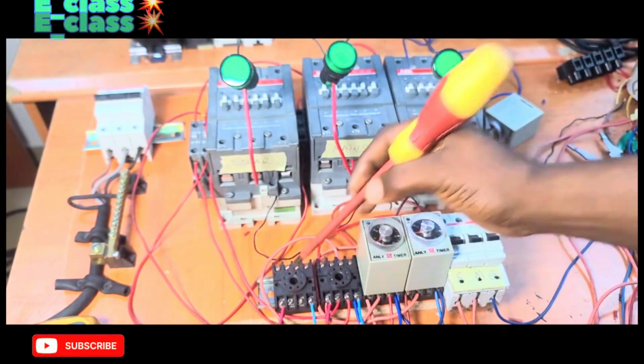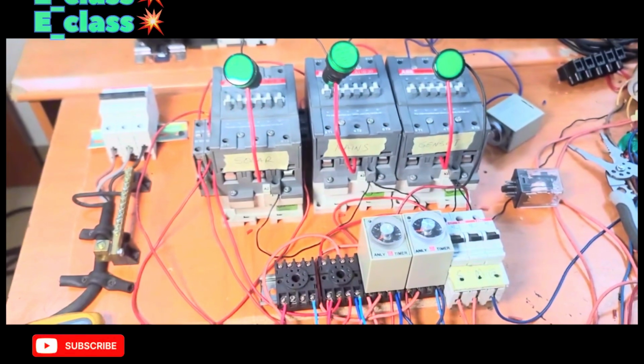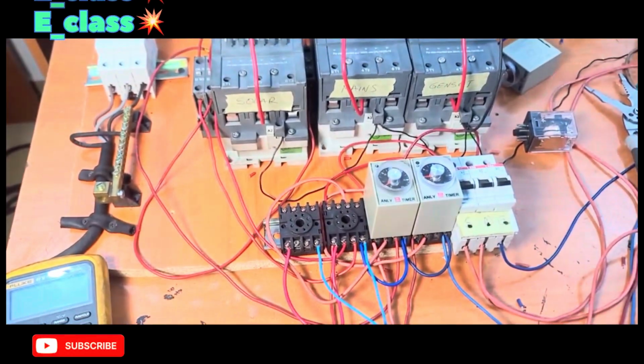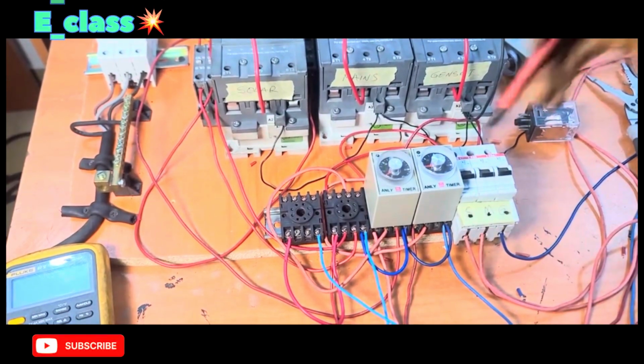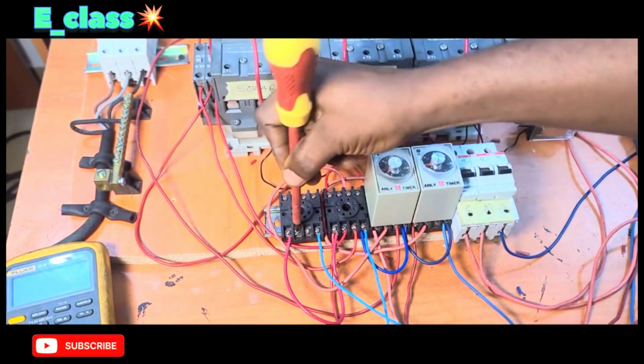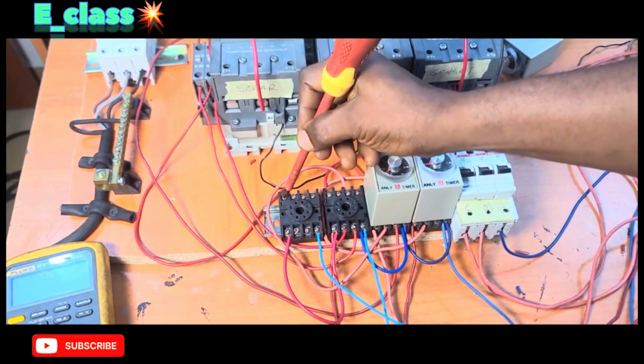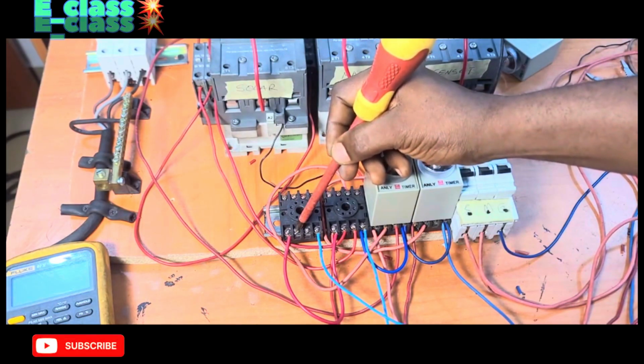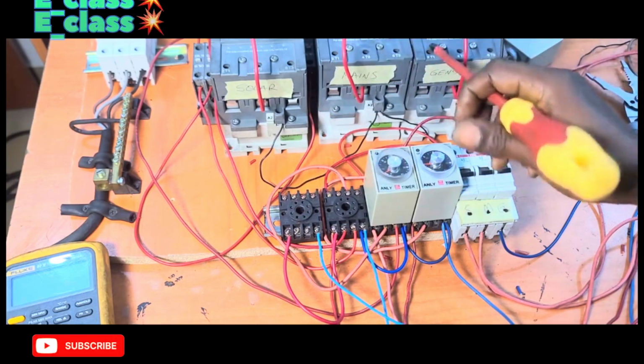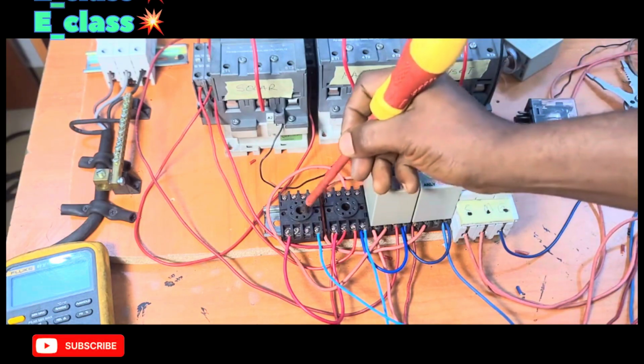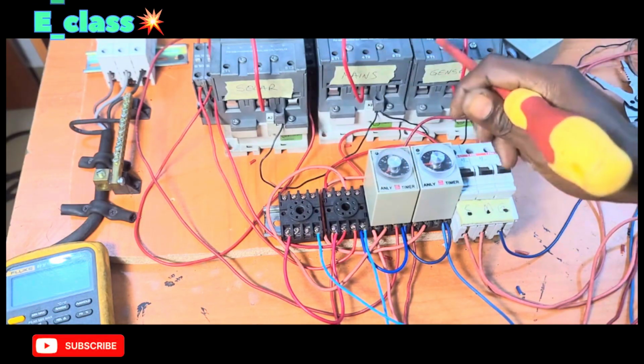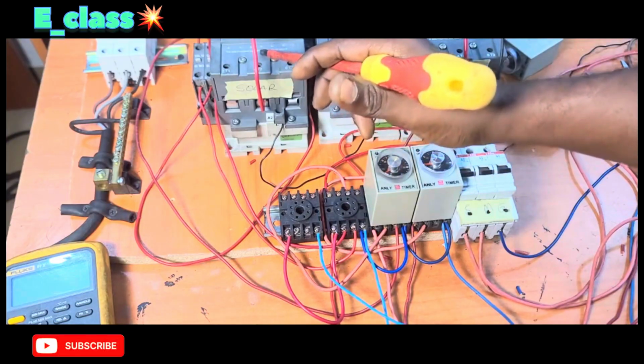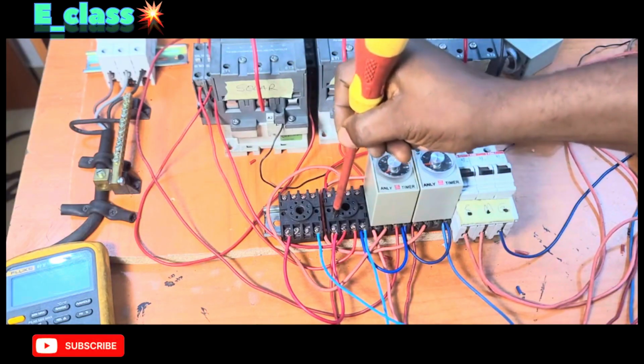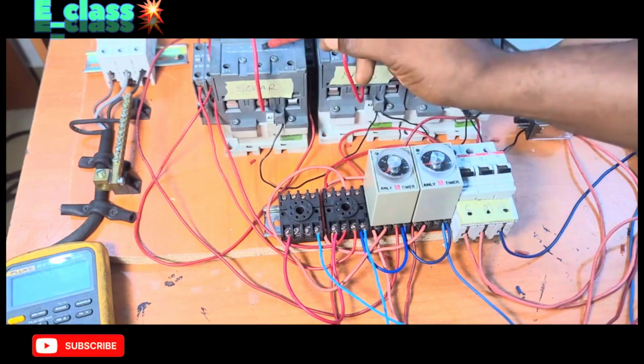All right, now we have some contacts on this guy. Okay, let me see if we can adjust this a bit. Right, so the same thing. This is common. This is pin 8, this is pin 5, this is pin 6. All right, we're going to make use of pin 8 and of course pin 5. They are normally closed. So this particular contactor will be on. Immediately power comes here, this normally closed will open, and then it will de-energize this one, and this one delays, and after the delay time that is set on this timer, it will energize.